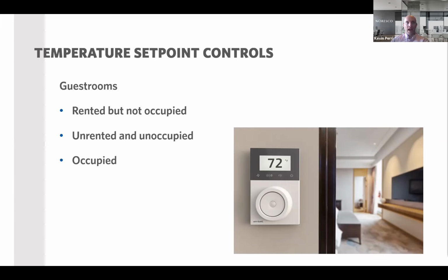One thing I'll pause for right there is that occupied category. If you think about it, it seems a little silly that there has to be a program that says an occupied set point. Usually, every time I've gone to a hotel room, you can adjust the thermostat to whatever setting you want while you're in the space. I think what they're hinting at here is that they want the BAS to limit what the occupant can control the space temperature to while they're in the space. It doesn't explicitly say that, but I think they're hinting at that, and who knows, maybe in the next code cycle that is going to be in there. But right now, it's just saying that in occupied mode, it goes to occupied set points.